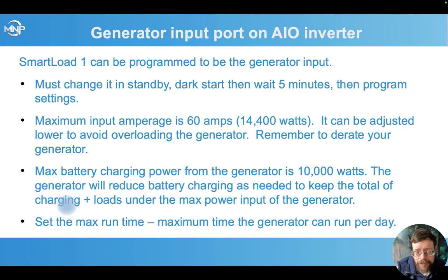Our maximum input amperage is 60 amps, 14.4 kilowatts, and this can be adjusted lower for smaller generators, so remember to derate your generator appropriately. The max battery charging power can also be set separately, and that's 10 kilowatts. So the 14 kilowatts is your total battery charging plus pass through to loads while the generator is running. The 10 kilowatts is the maximum amount to the battery charging, and it will back off on that to keep the total input less than the maximum that you set.